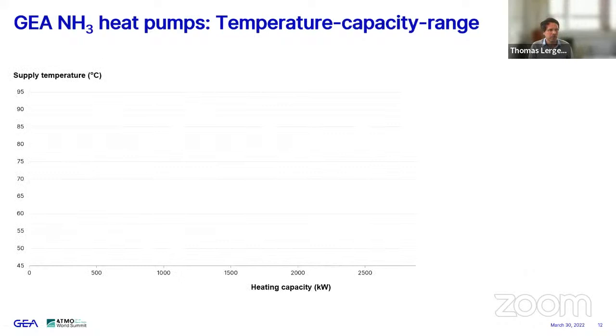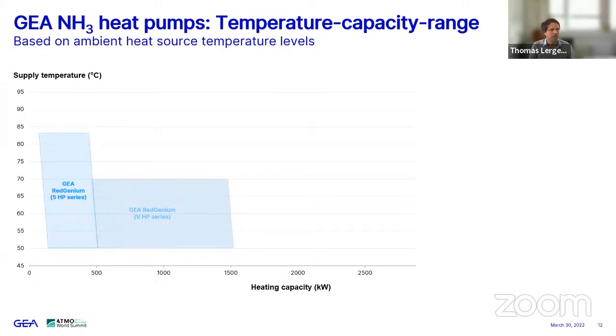So here's a chart showing the supply temperature and the heating capacity. If you're looking at a standard series with reciprocating compressors, piston compressors, we see two fields. Our heat pumps are able to provide hot side temperatures between 50 degrees Celsius and sometimes slightly above 80. Some compressors or units can provide only 70 degrees Celsius supply temperature. You see the range from a few hundred kilowatts to 1.5 megawatts of heating capacity. This is not a straight rectangle shape, but a little bit tilted.